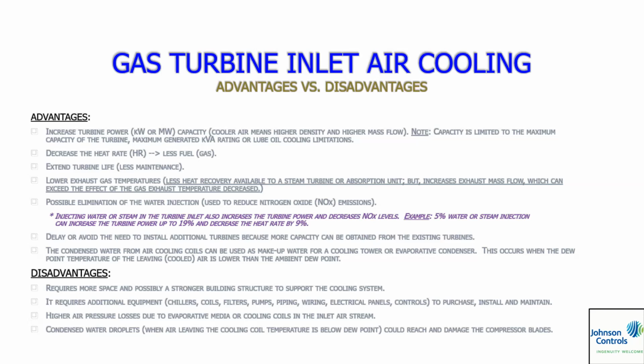Condensed water droplets, if you don't size it right, if somebody designing this doesn't know what the hell they're doing, then yeah, if your face velocity is too high, 2 things are going to happen. Pressure drop is going to go up, and you have moisture carryover, which means, just like an air handling unit coil, moisture carryover is going to get sucked in and could potentially damage the compressor blades. So I hardly ever see this because whoever's doing it in the gas turbine usually knows what the heck they're doing. But if they don't, shame on them. That's just basic design.